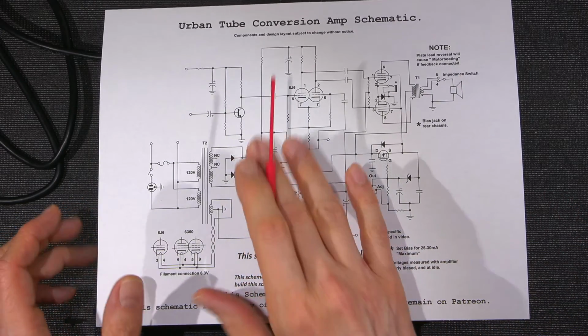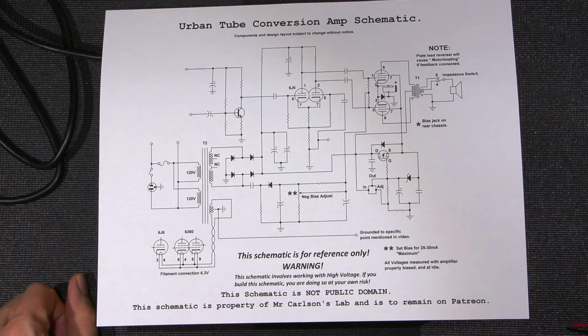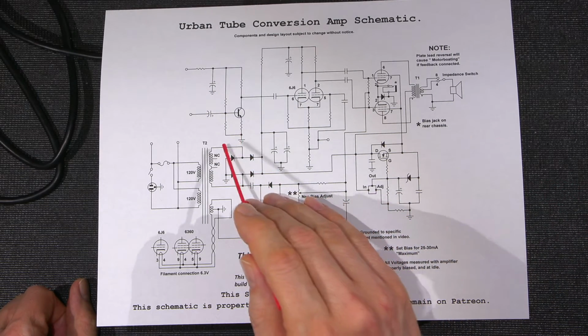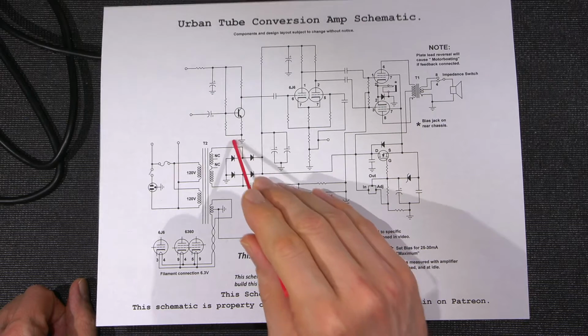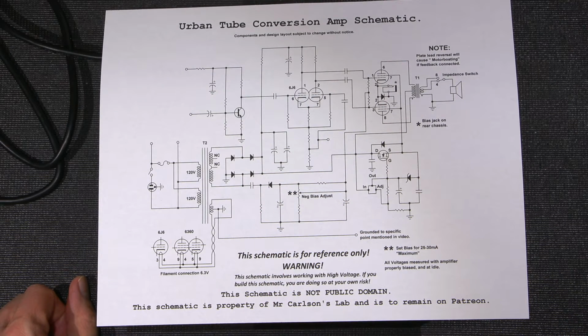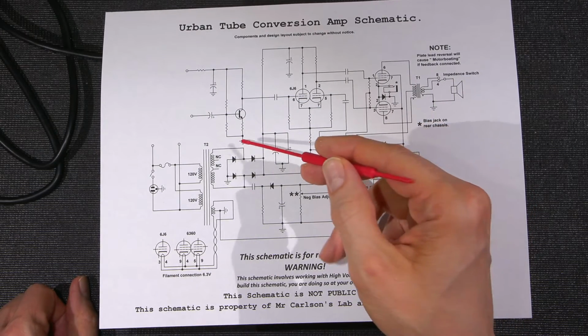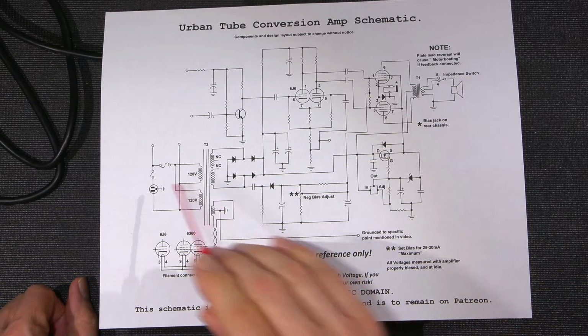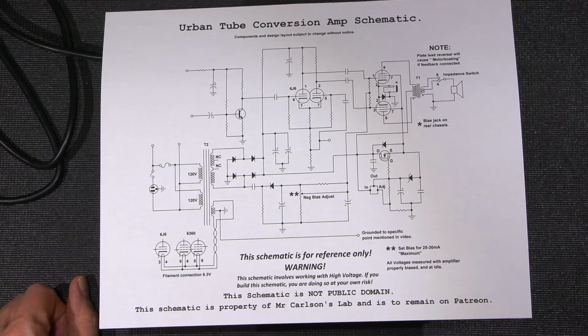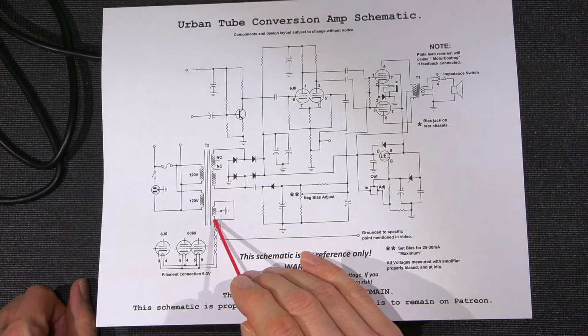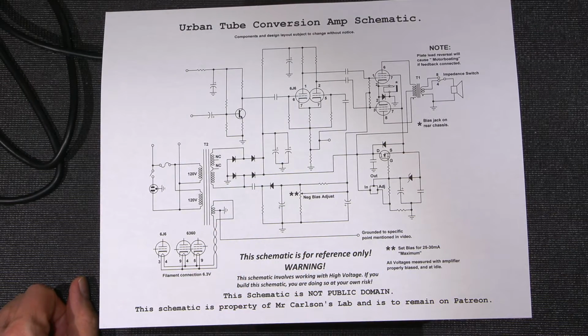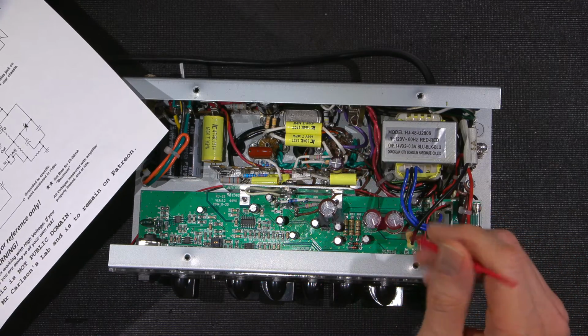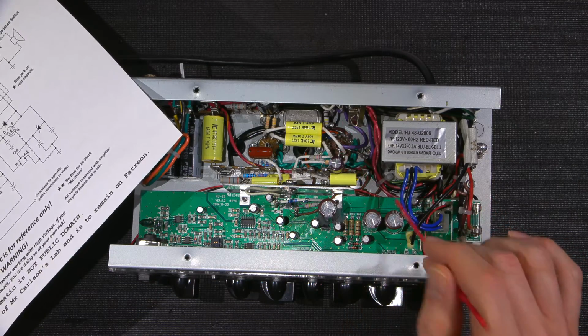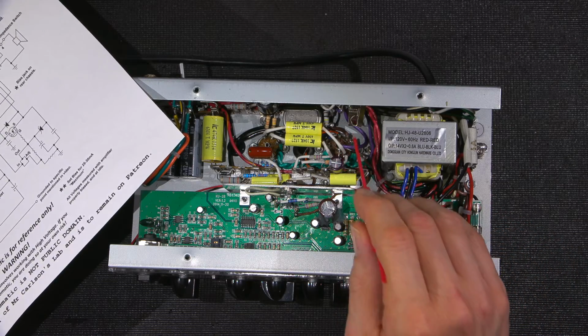Now, in order to test this and see what the current draw would be in a short circuit condition, yes, I have to short circuit things. So I short circuited the high voltage winding from one end to the other and turned it on for about a second, maybe a second and a half, and read it. If the high voltage section shorts, it draws about 4 and a bit amps on the primary side. If you short the filament winding from end to end, it draws about 1.5 amps, something like that. That's with the length of the wires themselves acting as resistance. That'll change as you shorten the wires up and get closer to the transformer, because the wires are acting as resistors at that point.